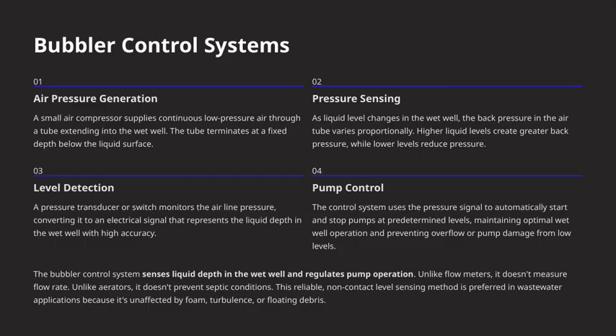Finally, this information feeds into the pump control system. Based on the pressure signal, the system can automatically start or stop pumps at specific levels. This helps maintain optimal operations, preventing both overflows and damage to the pumps from running dry.